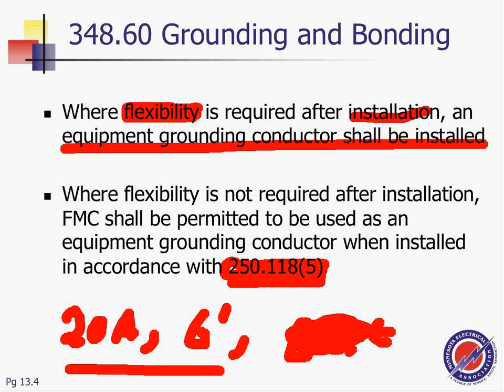You don't need it; you just put in that side the hot and neutral. You ground the fixture to the flex. You ground the fixture directly to the flex. Teaching you guys about grounding. I know old homes, guys, in the past, were wired with this type of wiring, and you are not supposed to use it as an equipment grounding conductor.